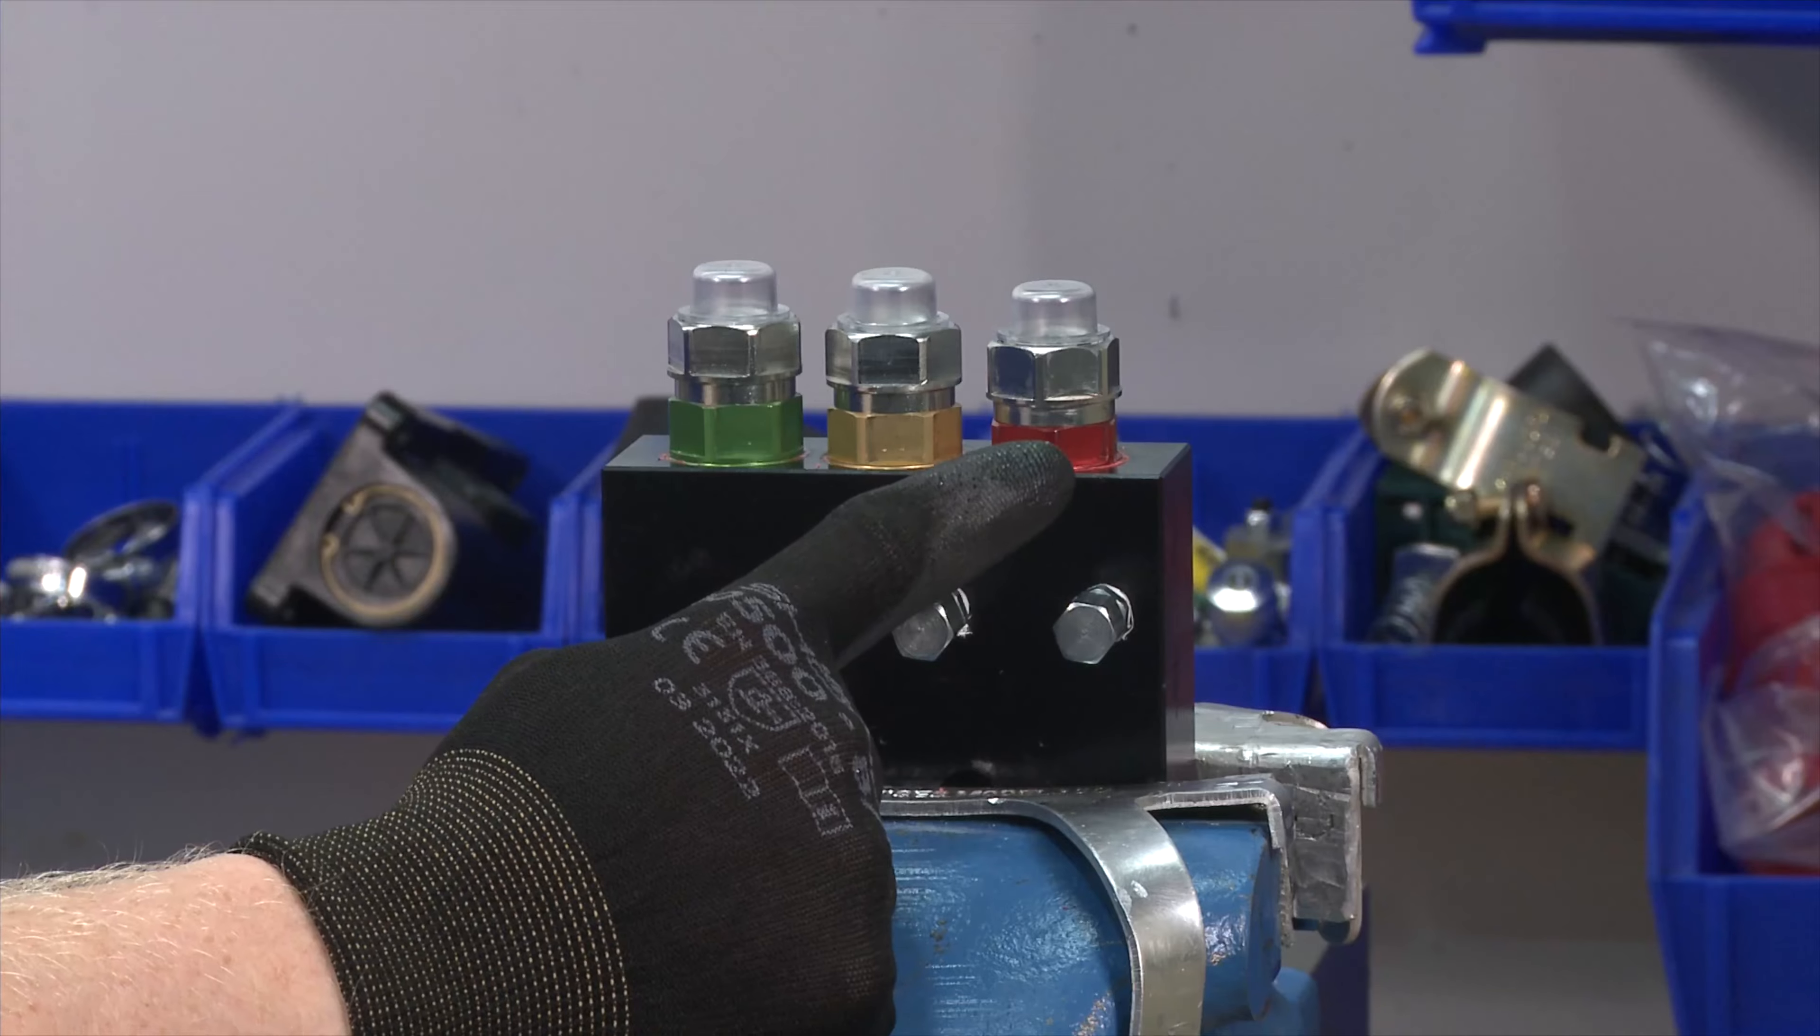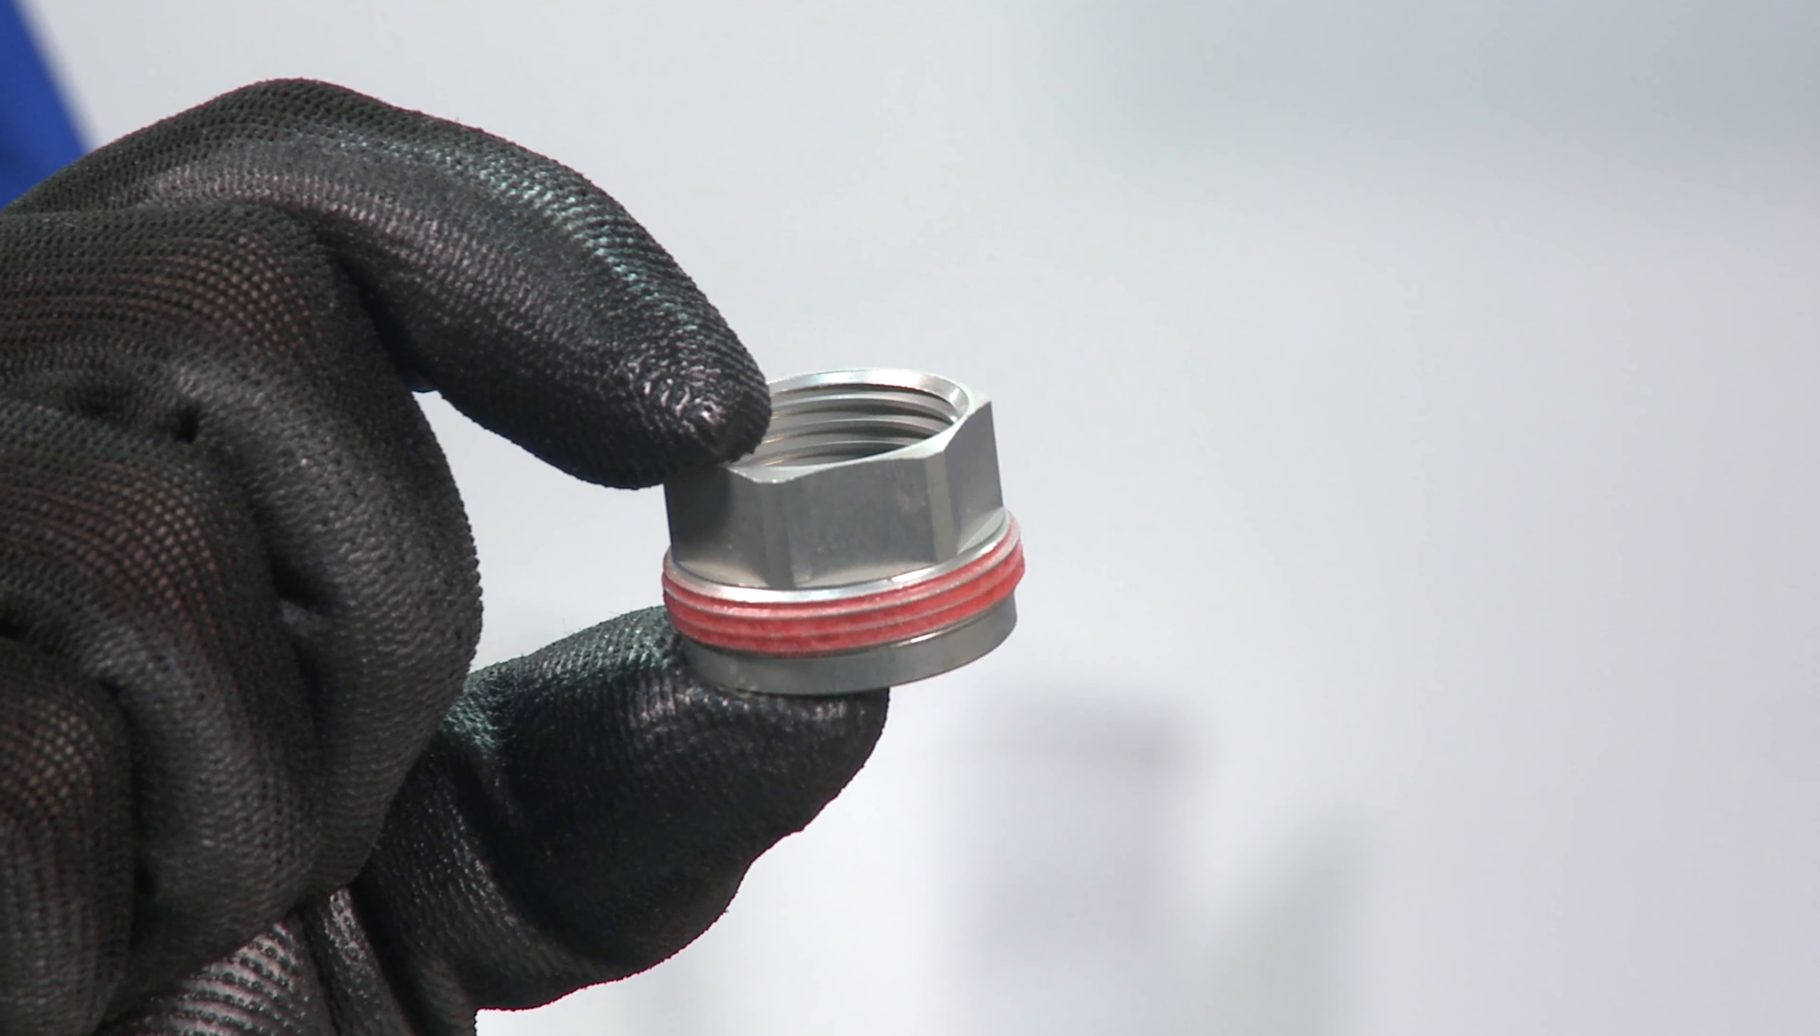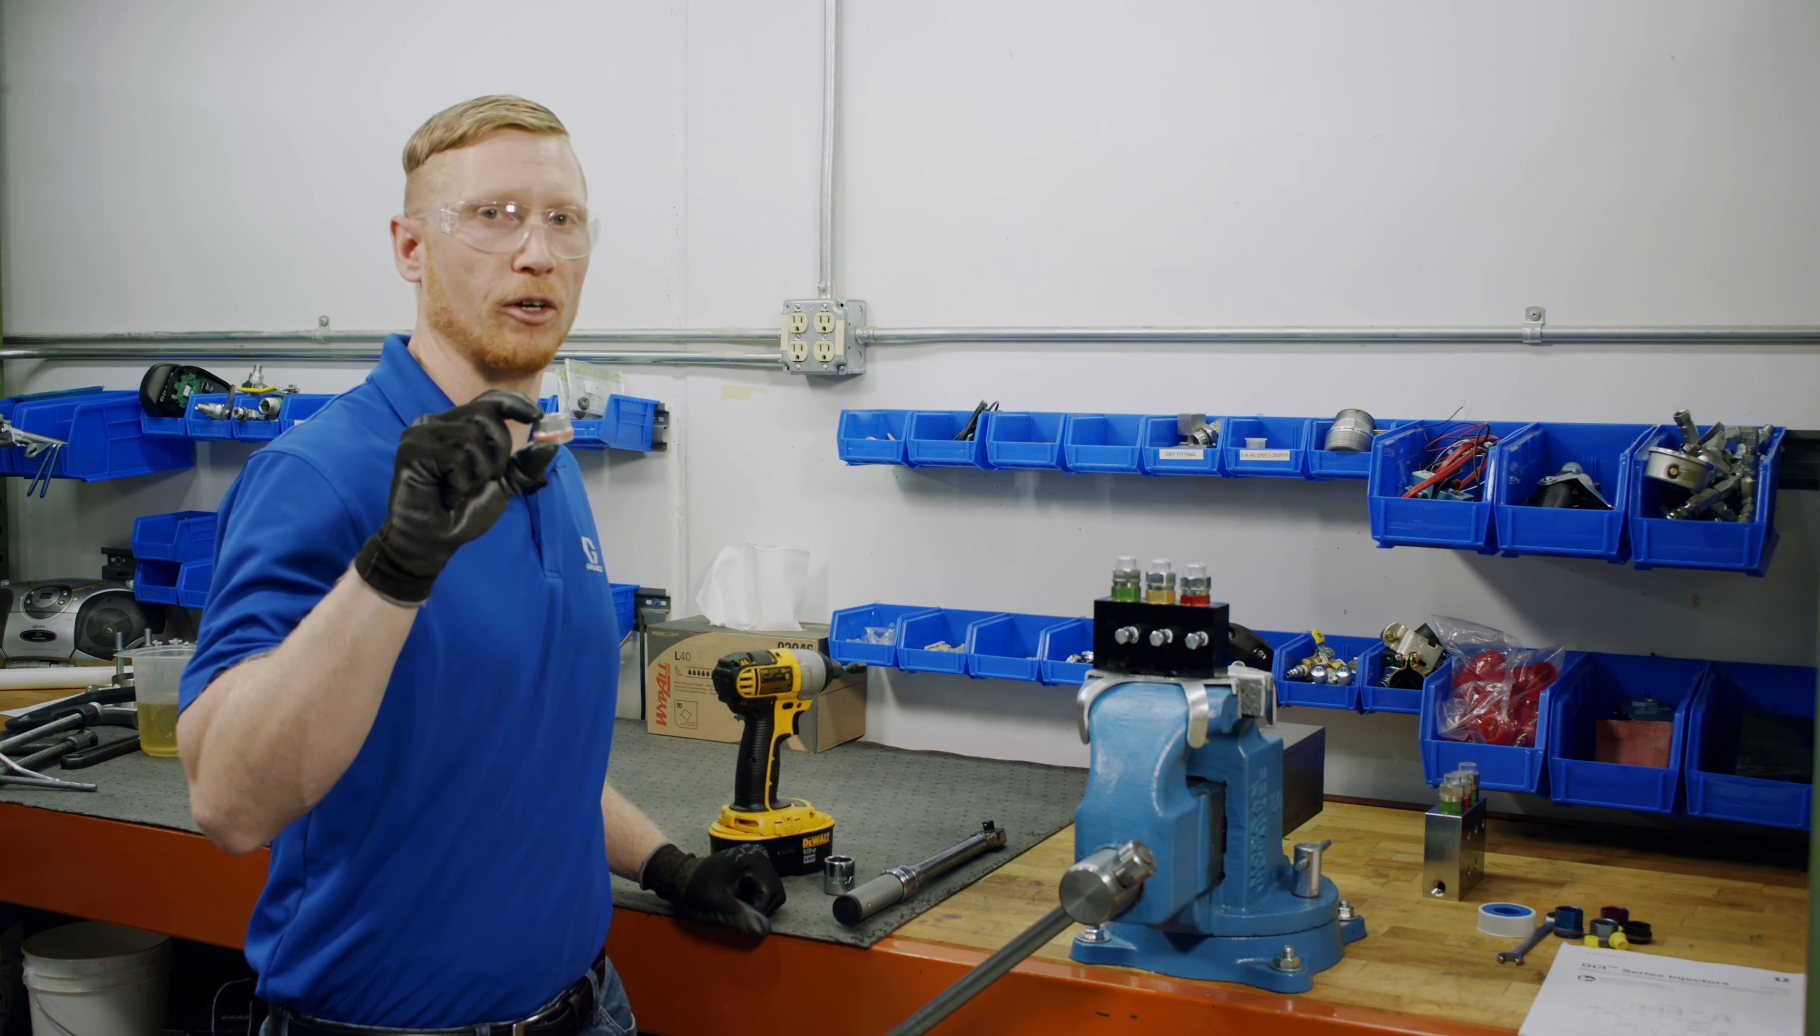I'm going to go ahead and change the output on this last injector here from 0.03 cubic inches a cycle, which is the red color, to 0.045 cubic inches. So if you have a customer that's saying they're just not quite getting enough lube to a certain point on a machine, you can go ahead and swap out these output spacers to get the desired output.